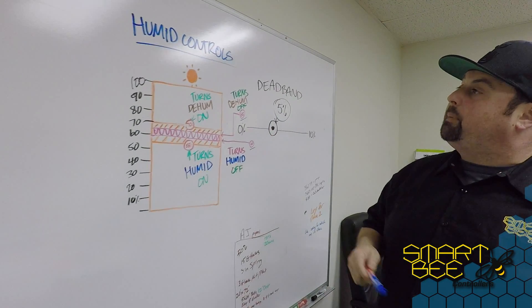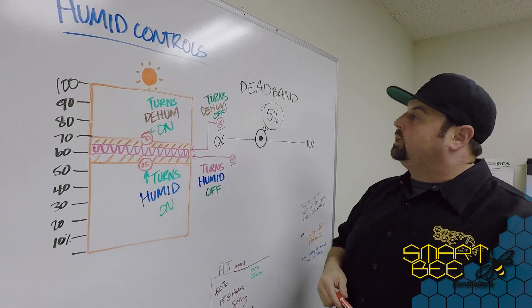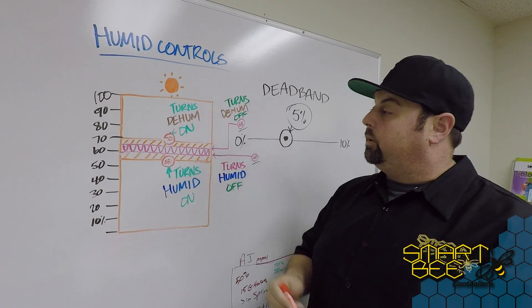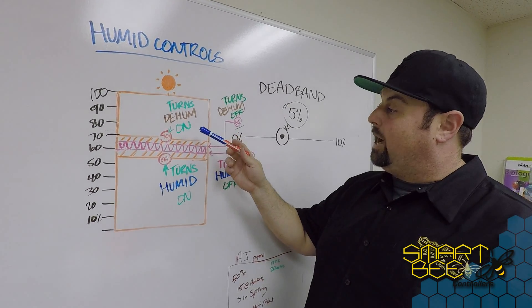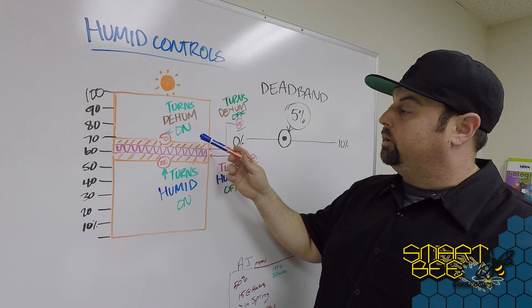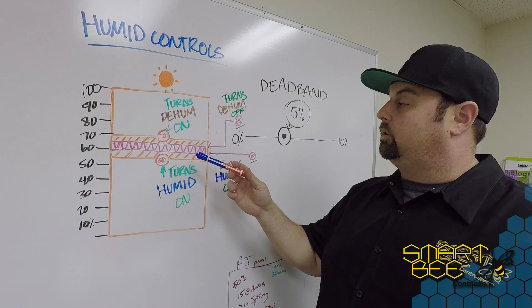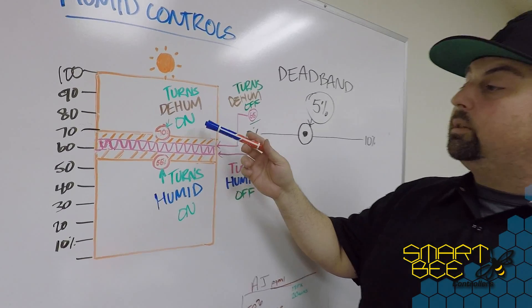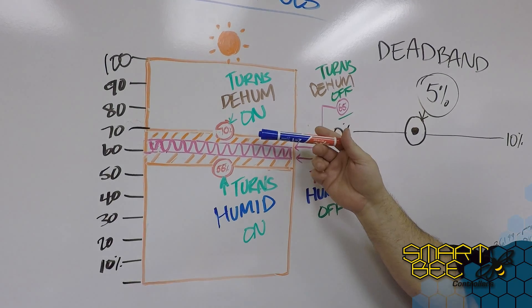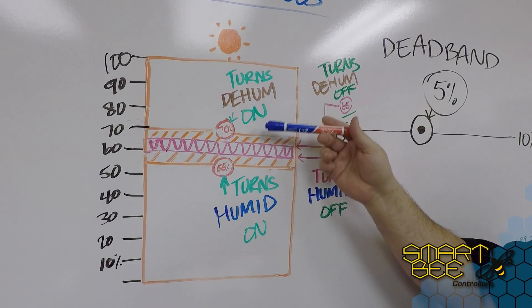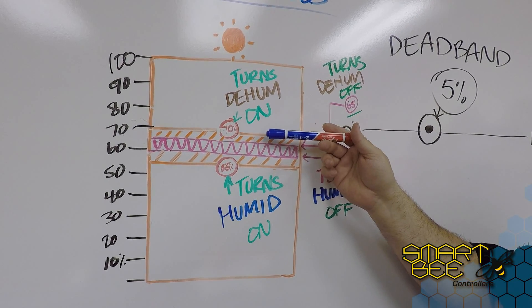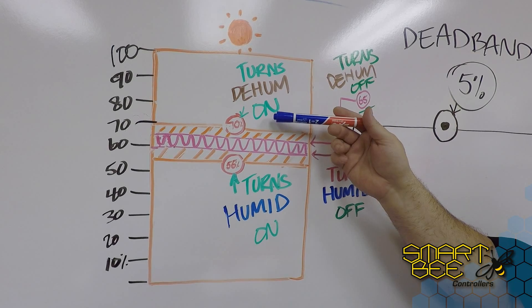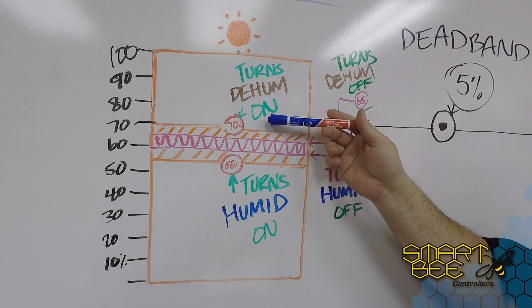Over here we have our dead band setting. The dead band came about because we found that our third-party appliances in our customers' gardens were cycling on and off too quickly.